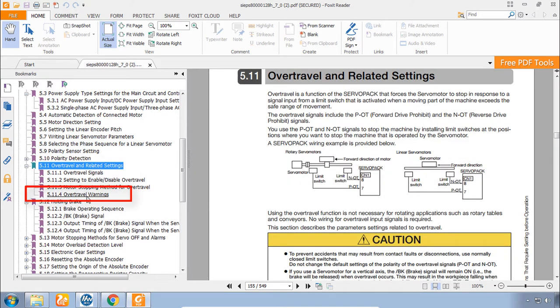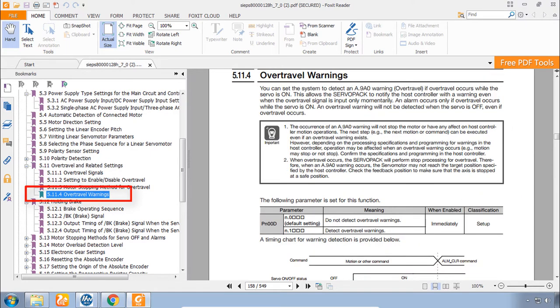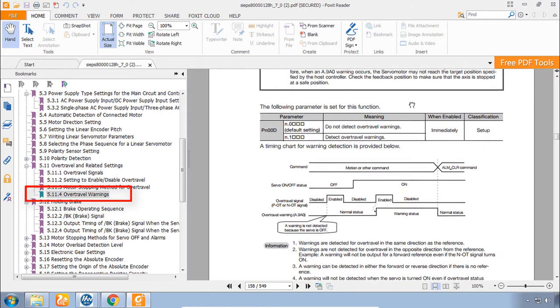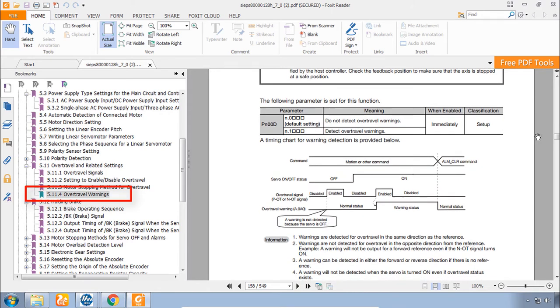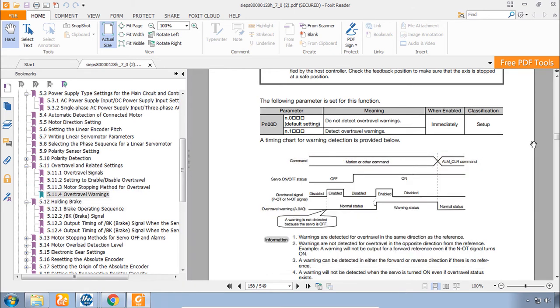And there's this new feature over travel warning. And without over travel warning the amplifier basically is just in an over travel state. It's not an alarm or a warning. The front panel says P and N depending on the direction of over travel. But this will give you a warning code which is more easily detected then by your controller. So this might be a good feature to implement.